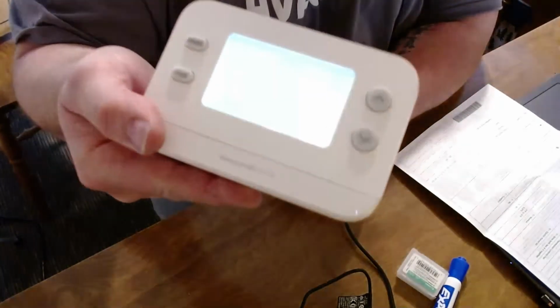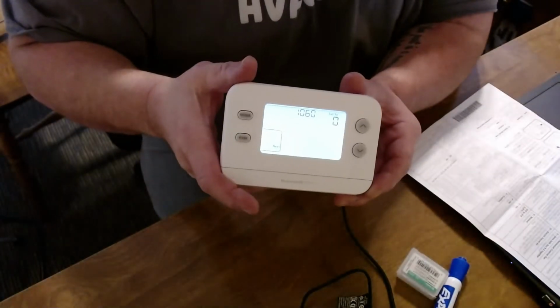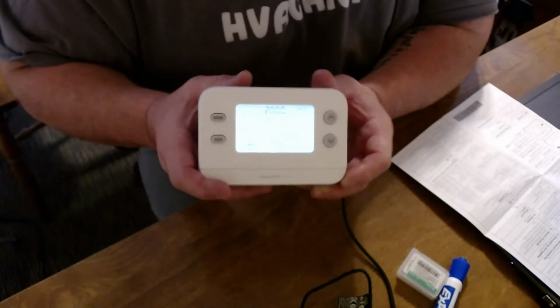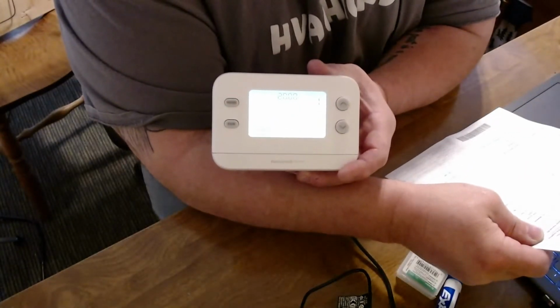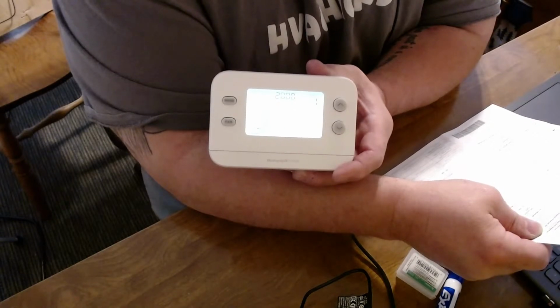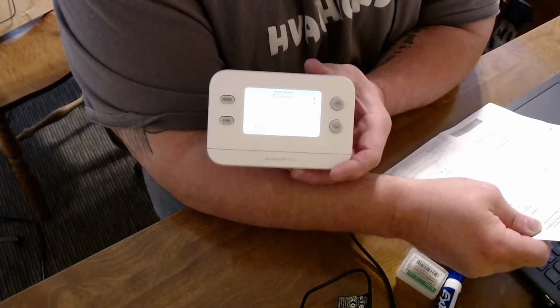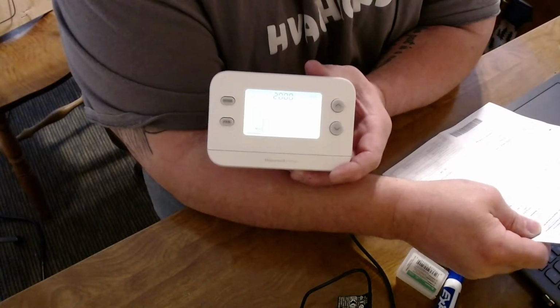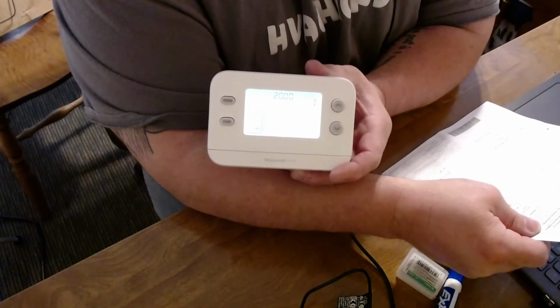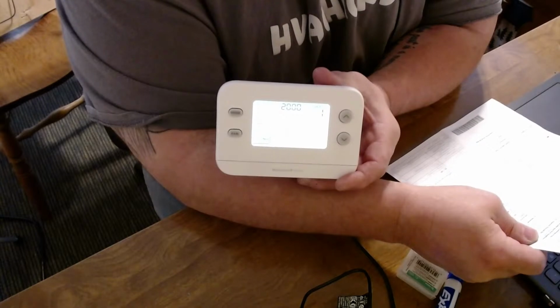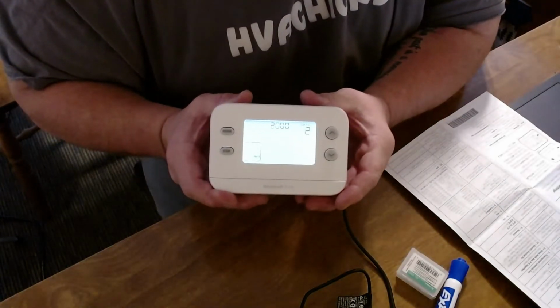The next is setting 160, outdoor sensor. Okay. 0 for none, 1 for wired. We're going to go 0. Then we have 2000. So we can go conventional forced air, standard. 1 is heat gas forced air, 2 is high efficiency gas forced air, 3 is oil forced air, 4 is electric forced air, 5 is hot water fan coil, 7 is a heat pump, air to air, 8 geothermal heat pump, 9 radiant heat, hot water radiant heat, and 12 steam. So you can see we can do several different styles with this system. So I'm going to set this for 2, gas forced air efficiency.